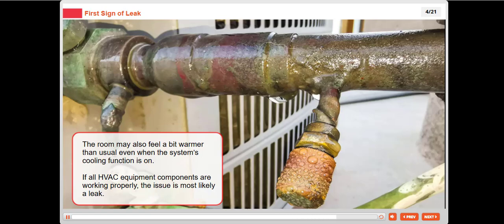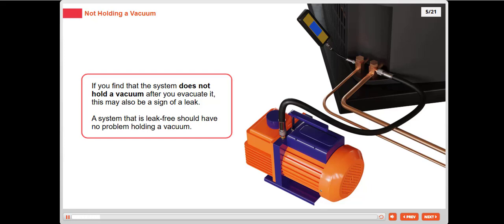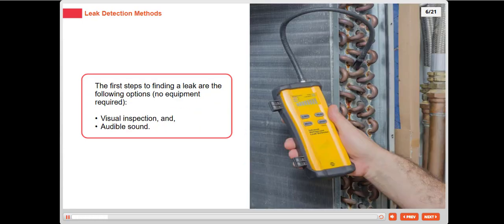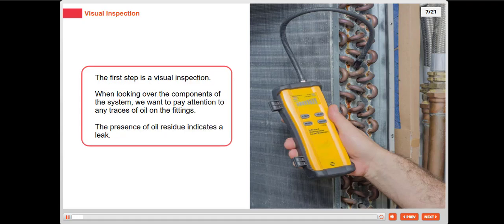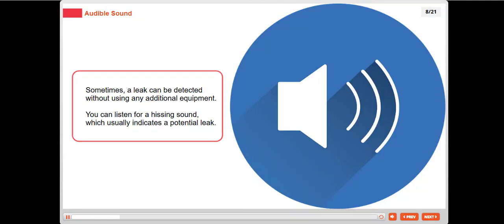If you find that the system does not hold a vacuum after you evacuate it, this may also be a sign of a leak. A system that is leak-free should have no problem holding a vacuum. The first steps to finding a leak are the following options that require no equipment: visual inspection and audible sound. The first step is a visual inspection. When looking over the components of the system, we want to pay attention to any traces of oil on the fittings. The presence of oil residue indicates a leak. Sometimes, a leak can be detected without using any additional equipment. You can listen for a hissing sound, which usually indicates a potential leak.